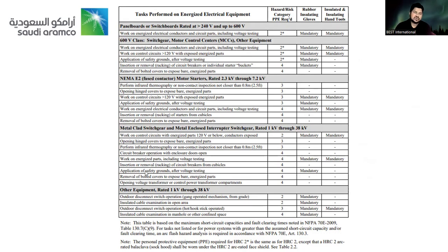So this table is also helpful to make you aware if you are near metal-clad switchgear or equipment rated 1 kV through 38 kV. Then the risk categories are 2, 2, 3, 4. So rubber insulating gloves are mandatory for all four, and insulated hand tools are mandatory only for outdoor disconnect switch operating, hot stick operated. So this is a criterion clearly mentioned. And I always encourage such information to be displayed on different notice boards, so the workforce can refresh their knowledge whenever there is any confusion.